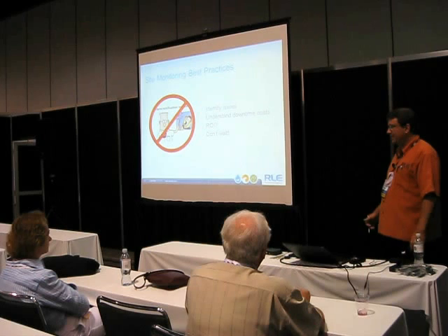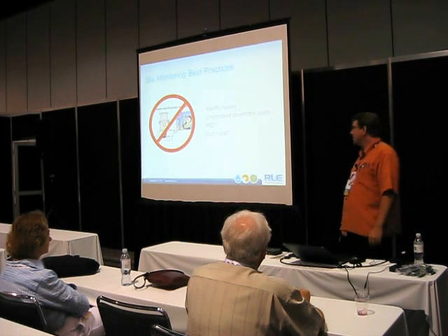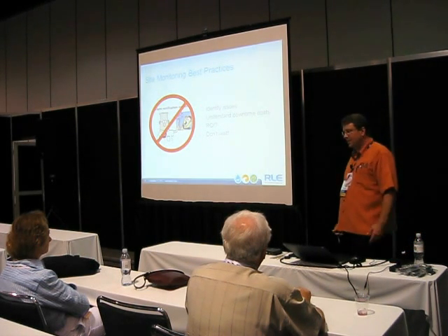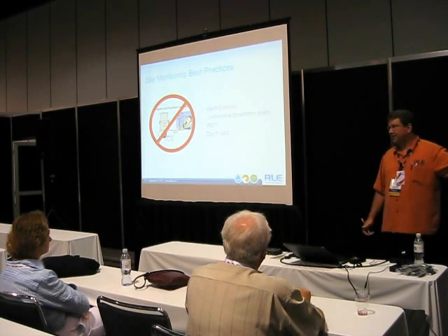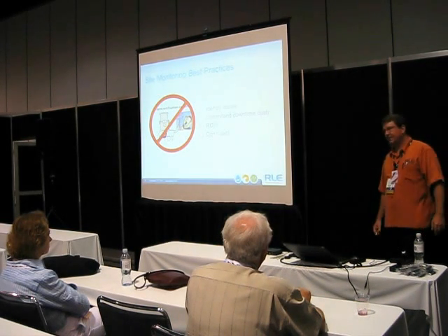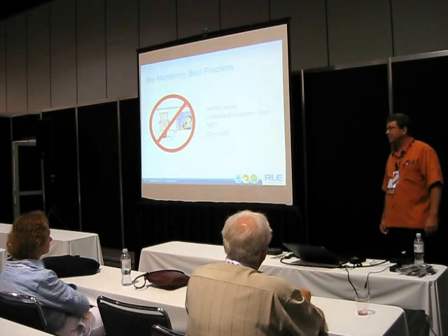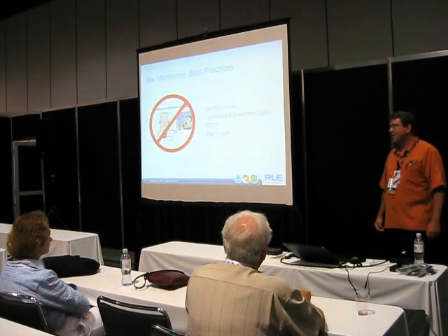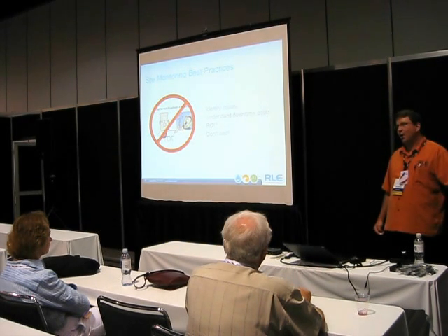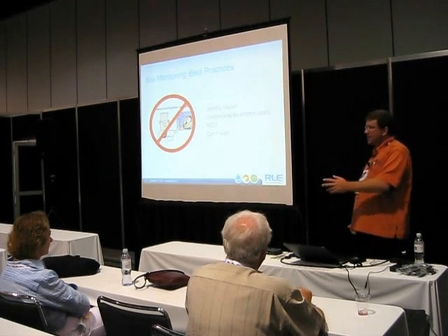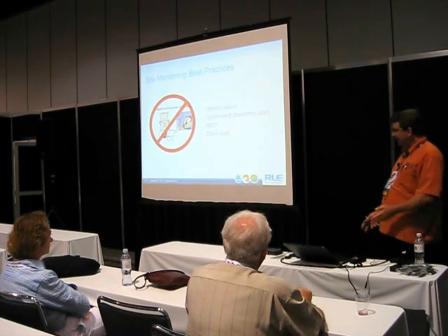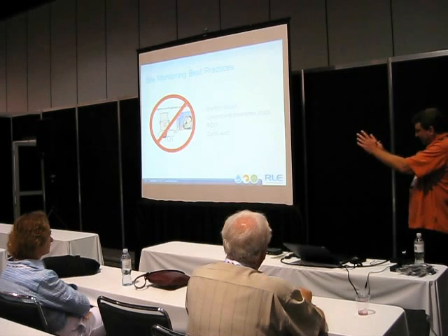A great example of that was the trading floor that I went out to. When I was talking to him on the final site survey, I asked what's on the outside of this wall right here, and the gentleman kind of paused and said that's the men's restroom. They had just never thought about the fact that they were sharing a common water wall until I got out there and asked that question. I've been out on sites with a multi-million-dollar expansion, and the guy's showing me, here's a cabinet right here.